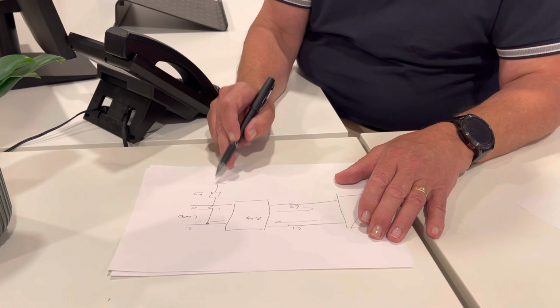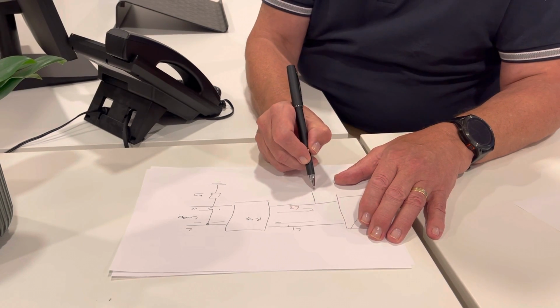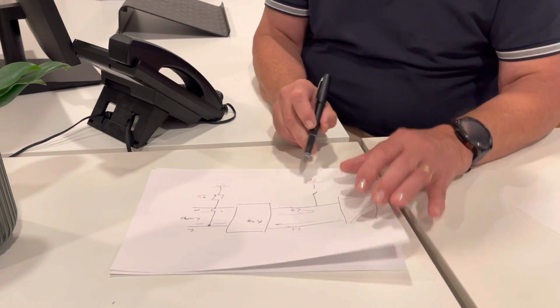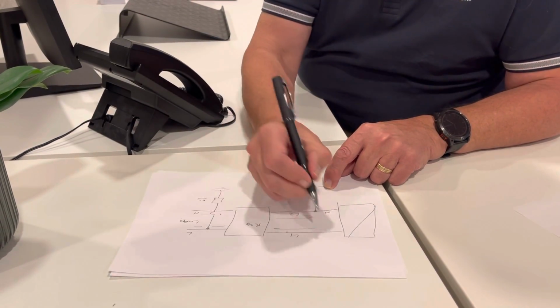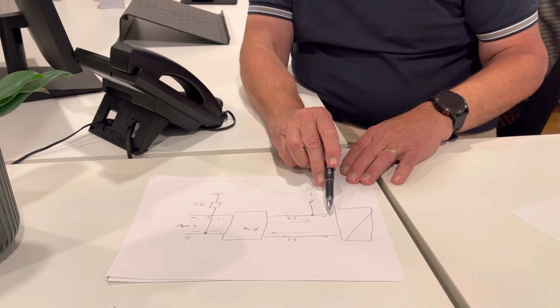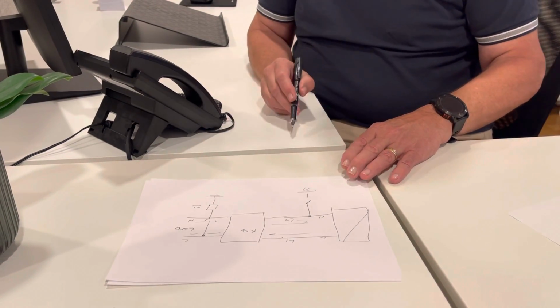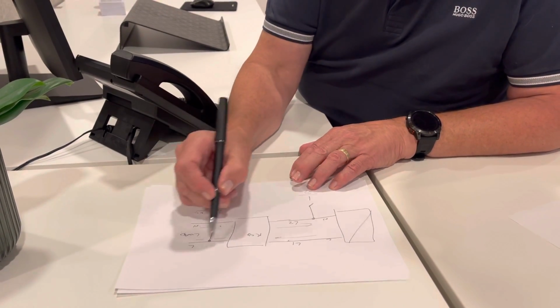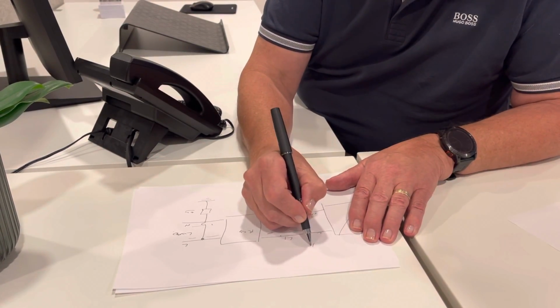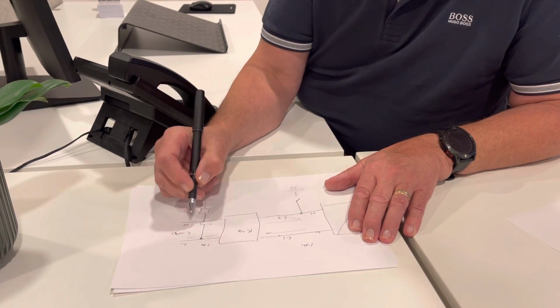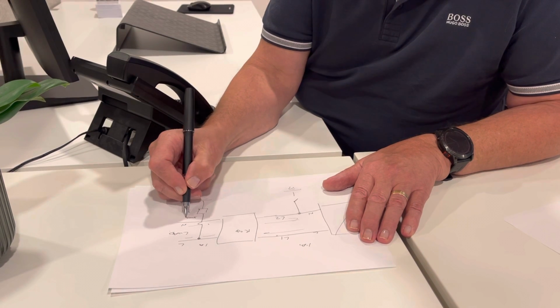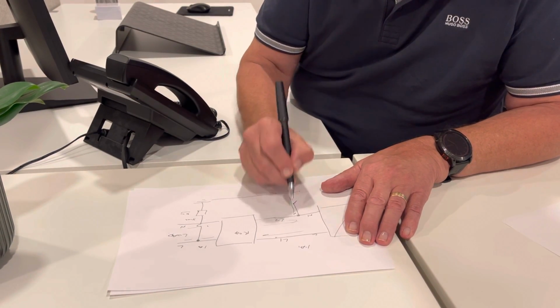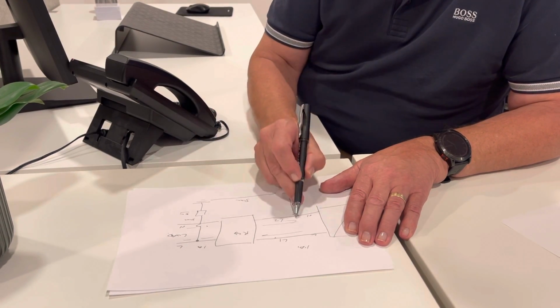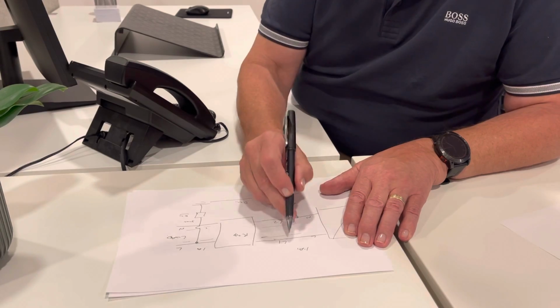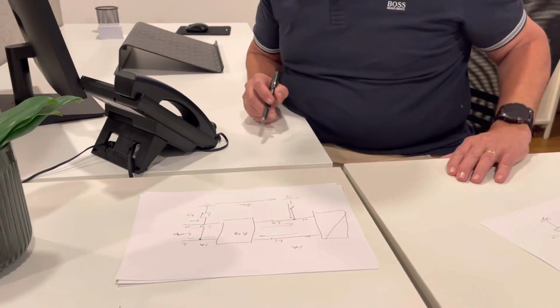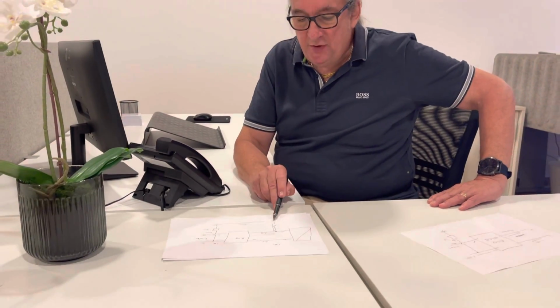The only way this energy can flow through here is if on one of them, I use a relay and I put it to ground. And by putting it to ground, and I call it the neutral, and I call it the live, by putting the cable which I call neutral to ground, then it can allow a flow. Because if I touch here, some of the energy coming in, so I put 1 amp here, but some of the energy, maybe 50 milliamp, will flow through the ground, and it'll come back here. So some of it will flow this way, and some of it will flow back this way. And there's going to be an imbalance and therefore the RCD will work. And it only can happen by putting this bonding in here.